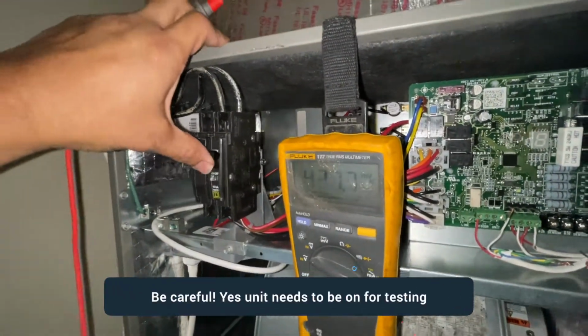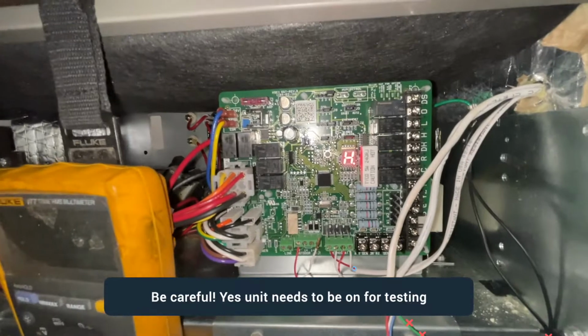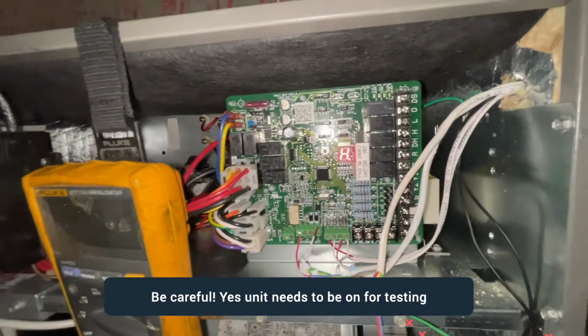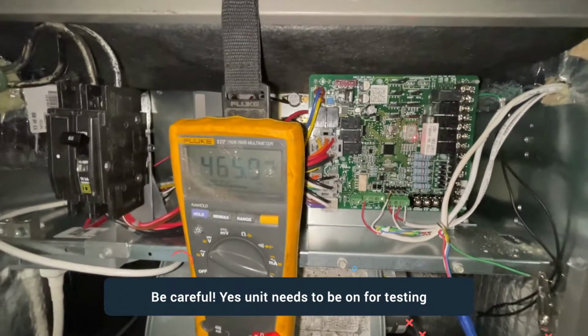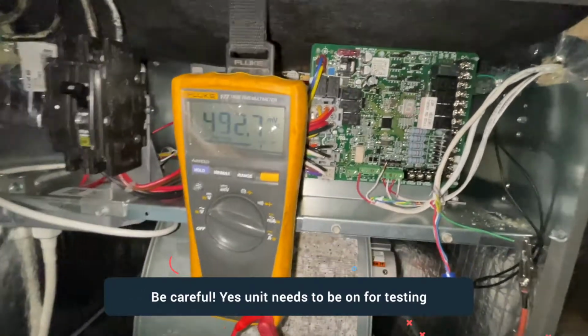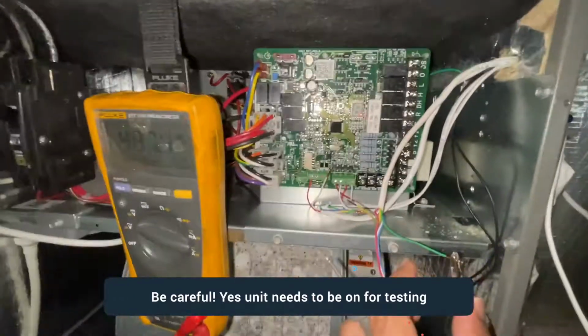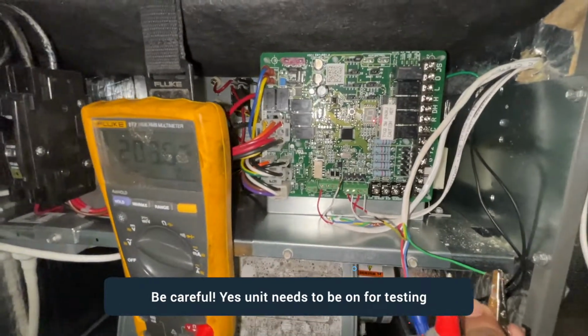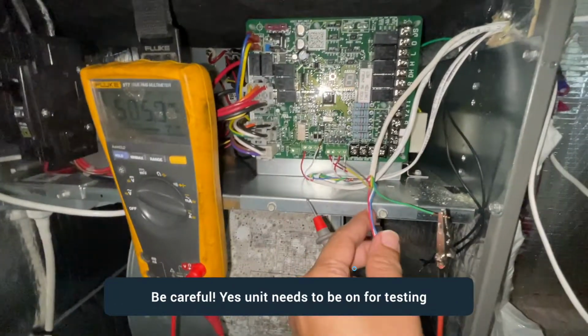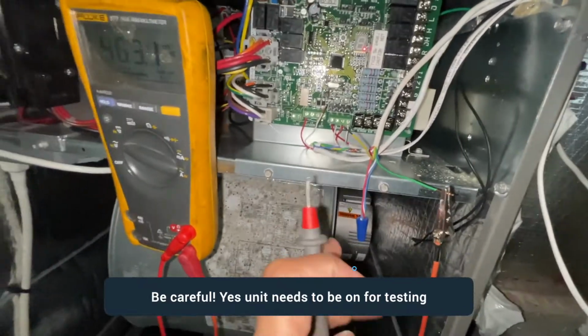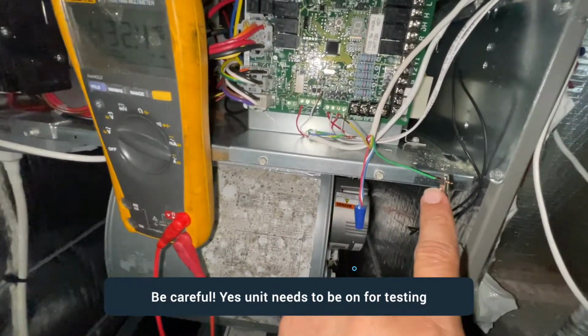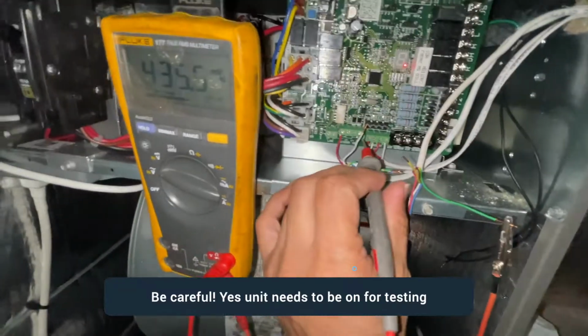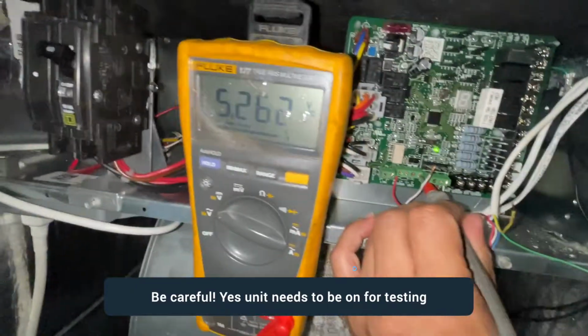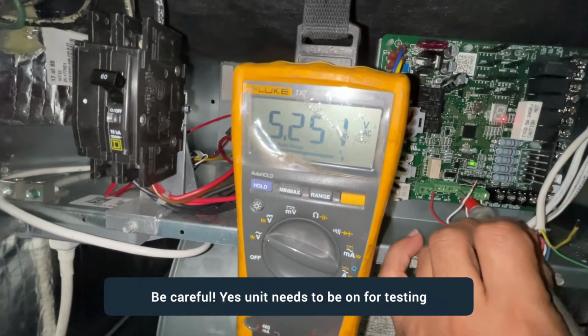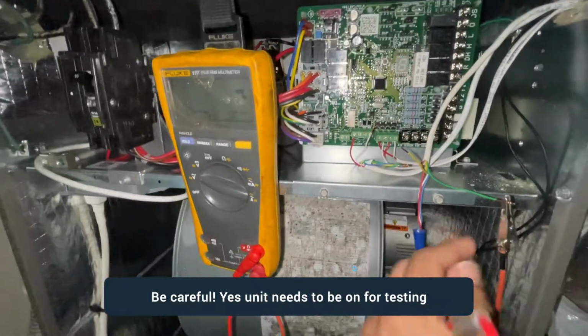Let's go ahead and turn the power on. Now the unit is coming on. Let's wait for it to stabilize. There you go, it's on. Now, right here, since I'm measuring transient on this wire, I connected one lead on here, and the other one I'm going to touch on the common side. If I touch on the common, you can see I'm getting 5 volts AC, which is a lot lower on this wire.